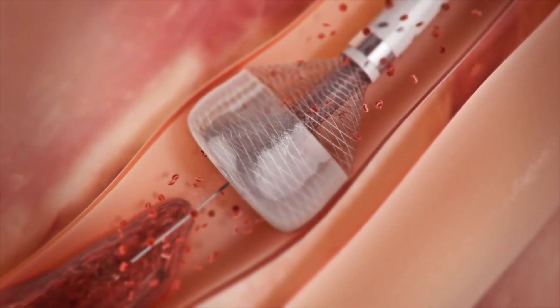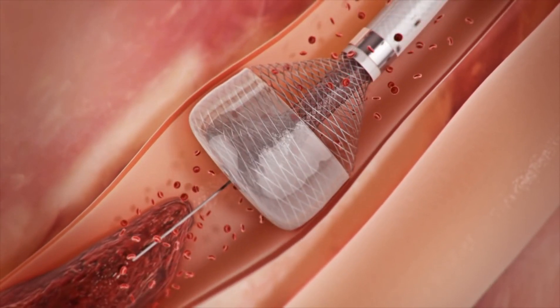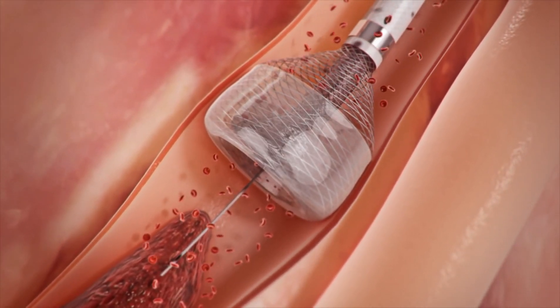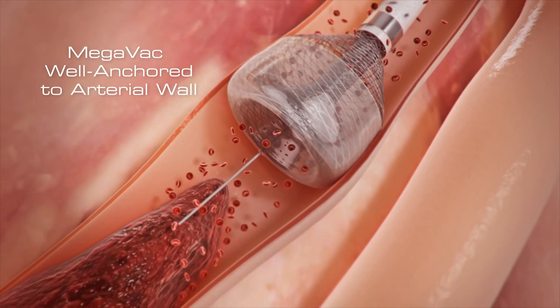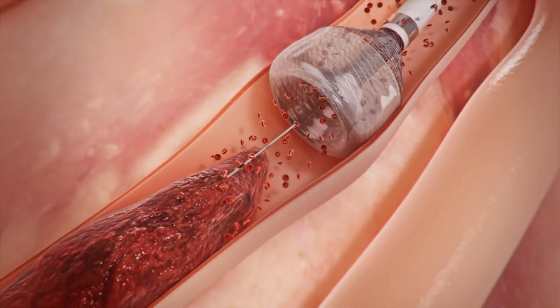The patient's blood pressure, along with the radial force of the funnel tip, combine to press the device against the arterial wall, anchoring the catheter firmly and safely. The outward expansion of the MegaVac anchors and centers the device, and can be used as an anchor for other devices, crossing tight lesions or tortuous vessels.